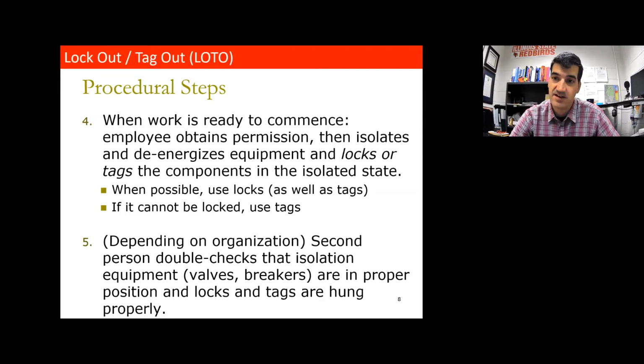It's not that hard to make a mistake. You're at the end of a 12-hour shift, hanging tags and de-energizing things, looking for the right circuit breaker, you look down and back up, then operate the wrong one. It happens, unfortunately. So it's important for the second checker to verify the tags were hung and the circuit breakers de-energized in the proper locations.